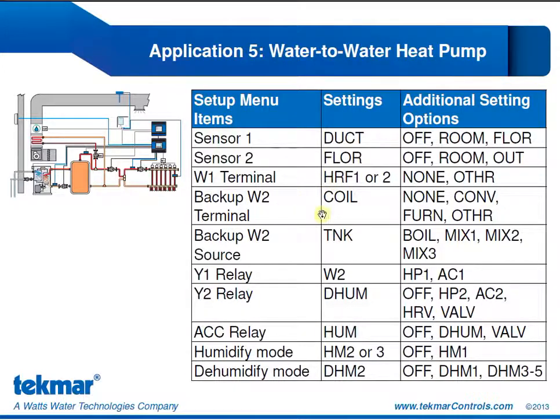Here are the essential settings. Sensor 1 will be configured for the duct sensor, and sensor 2 would be configured for the floor sensor if you're using that slab sensor. Our W1 terminal is set for our radiant floor. Backup W2 is set for coil. And again, it's hydronic, so we have to specify the backup W2 source. In this case, it's coming off the tank, so tank is our source.